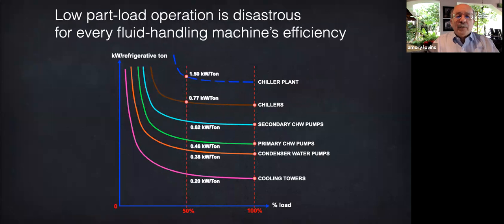Fluid handling machines lose efficiency rapidly at part load. This typical chilled water system for cooling a big building runs at a total power of 1.5 kilowatts per refrigerative ton of cooling at 50% load. Even better at full load, that is towards the right, but off the chart awful further to the left at a third or a quarter of full load. It's just terrible. The pumps can easily lose half or more of their full load efficiency when they're running at low load.